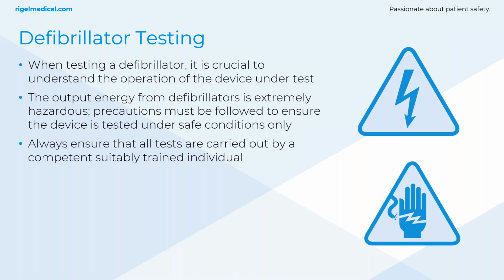First, what we need to do is look at the device under test. Every defib manufacturer and model has its own procedure and settings. You need to make sure you understand what those considerations are first. Also, we need to ensure that tests are carried out by competent individuals. We're using test loads to verify the specification of the device. We just want to make sure that there's no one in contact with the electrodes, and we double check all those connections. What you find now in a lot of biomed departments is they're testing with just two 4mm insulated leads going directly into the analyzer, as opposed to just using pads, because there's always a risk inherently involved with defibs, and it's a serious one. Although unlikely, it's still something we should try and reduce as much as possible.